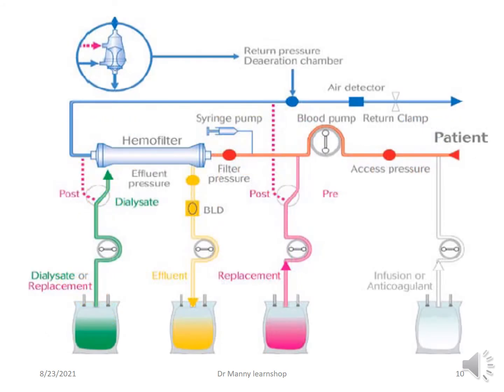So the circuit essentially is red access line, pulls blood out of the patient to be cleaned in the hemofilter, then is returned to the patient. But before it's returned to the patient, it goes through the dialyzer. The dialysate solution pulls off things like urea, creatinine. If the potassium is high, the replacement solution dilutes. It dilutes the blood, and in doing so, the pump automatically will pull off more fluid. And in doing that, you have blood purification.